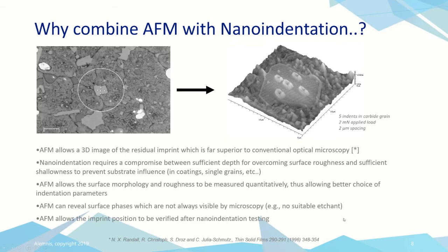Now, the AFM also allows us to measure the roughness of the surface. It allows us to choose an area of the surface that is suitable for nanoindentation, and it can reveal phases that we wouldn't be able to see otherwise. Okay. It also allows us to image the imprint after indentation and therefore understand what is the exact material's response.